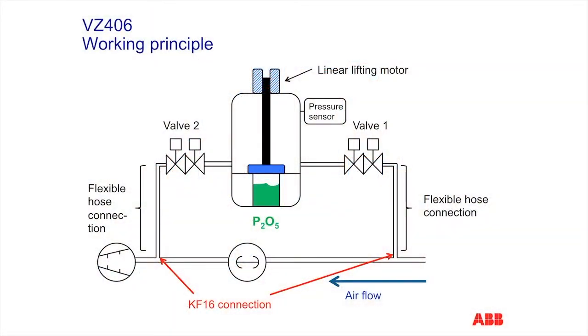A diagrammatic view of the VZ406 is shown here. It has a measuring chamber that contains a closable chamber within it that contains phosphorus pentoxide. This material is corrosive and toxic. Consequently, gloves and eye protection are mandatory. Be aware of the proper cleanup procedure in the event that any material is spilled. Valves 1 and 2 and the linear lifting motor are controlled by the computer. The pressure sensor can be read remotely by the computer.